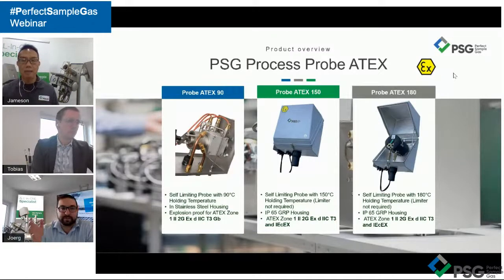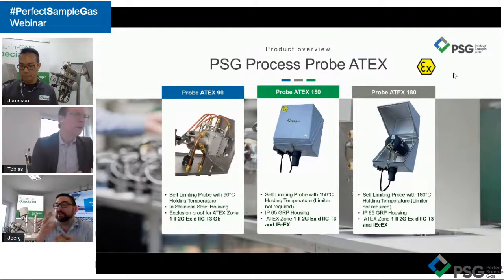As you are still in the field of a CEMS, but just as determined as a zone 2 or zone 1 application, you still want to have those options you're familiar with from a CEMS application. You still want a back purge system, maybe a pressure reduction valve, maybe the valves already pre-assembled at the probe. That's why we say we're working with the same filtration element from a technical point of view, where the gas comes in, gets filtered, and goes out. But of course all the heating elements need to be suitable for the ATEX environment, and some things around are changed to make this happen.